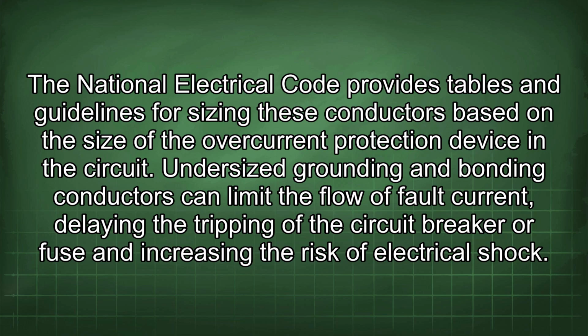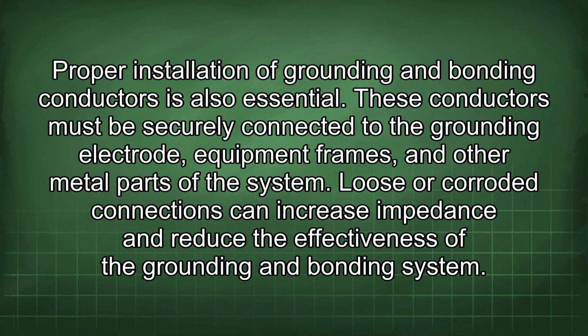Undersized grounding and bonding conductors can limit the flow of fault current, delaying the tripping of the circuit breaker or fuse and increasing the risk of electrical shock. Proper installation of grounding and bonding conductors is also essential. These conductors must be securely connected to the grounding electrode, equipment frames, and other metal parts of the system. Loose or corroded connections can increase impedance and reduce the effectiveness of the grounding and bonding system.